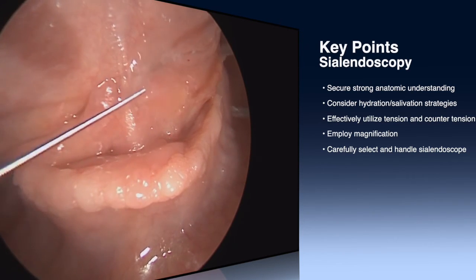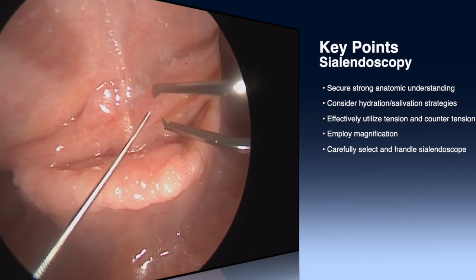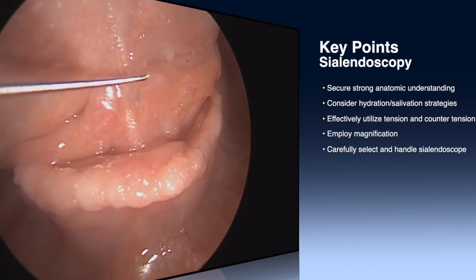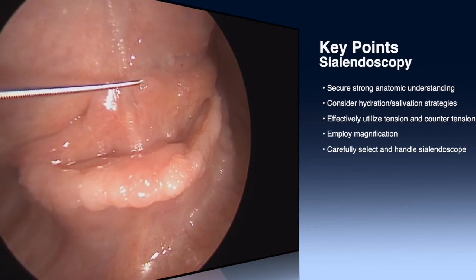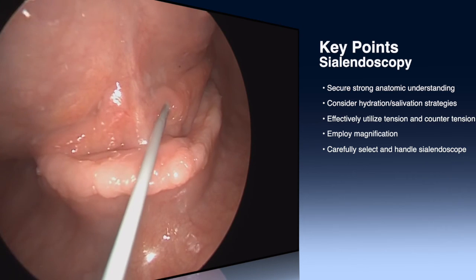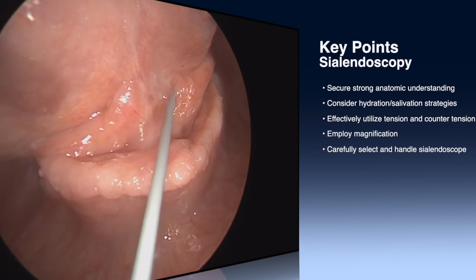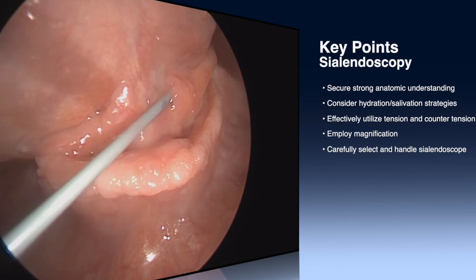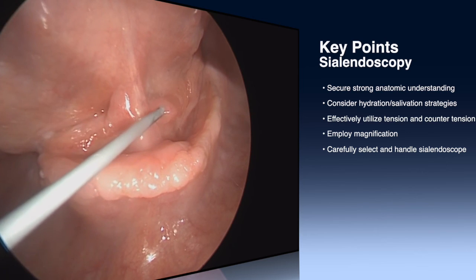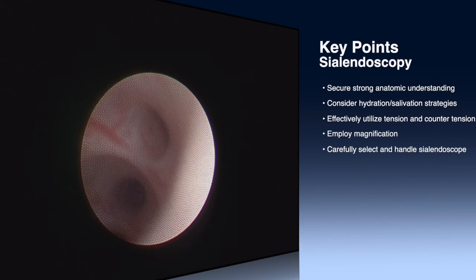In the case of the submandibular gland, the countertension can be provided with a curved tooth forceps or with countertension in the floor of mouth with the non-dominant hand. Magnification in the form of loupes, exoscopes, or a microscope is essential for successful cannulation and dilation of the very small duct papilla. In general, I'd like to use a slightly larger sialendoscope — the 1.1 and 1.3 mm sialendoscopes are a good workhorse for diagnostic sialendoscopy, with the 1.6 mm sialendoscope particularly helpful for interventional sialendoscopy. The sialendoscopy equipment is extremely fragile and should be handled with great care in order to reduce the risk of fracture of your lenses, which is a costly repair. This concludes the video on diagnostic sialendoscopy. Thank you for watching.